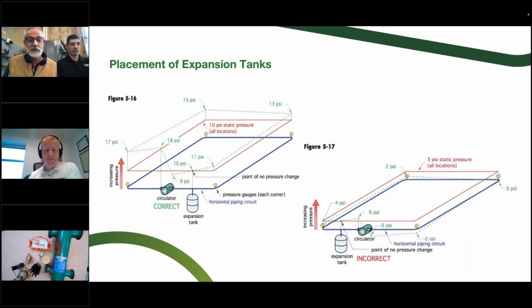And a lot of times it's this placement of this expansion tank. And what makes this worse, if they went to a job that used to have an old B&G Series 100 pump, and they put in a pump with a little higher head, like a 1558, even a 007, you can make these numbers worse because you've added a little bit higher head pump, and you can pull this pressure down to subatmospheric, maybe even sooner in the system. So it's related to the pump, it's related to the circuit, but it's an easy thing to fix. Either move the pump to the other side or move the expansion tank to the inlet side of the circulator.